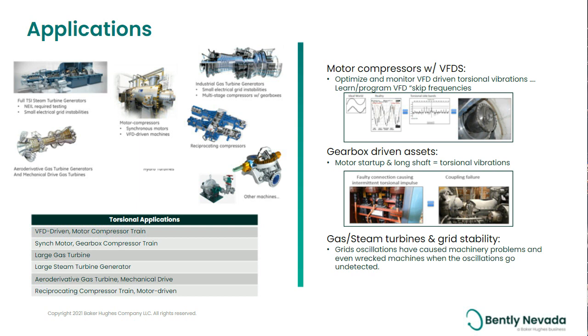So the grid has to be able to couple not only these high demand short use cases, but also the everyday baseload use cases as well. There are methods, of course, to help mitigate and dampen these grid oscillations, but if you're not detecting or at least monitoring and evaluating the impact these are having on shafts and machine trains due to torsional vibrations, that can go unchecked and lead to additional faults and failures in the future.